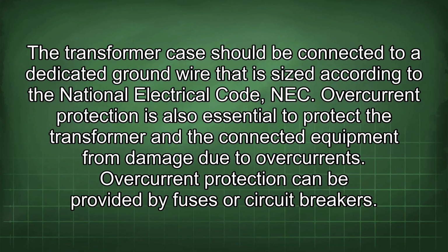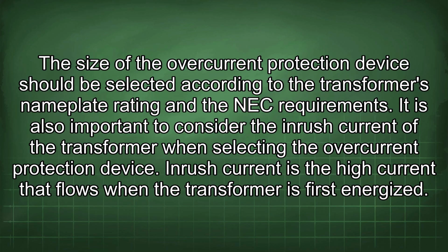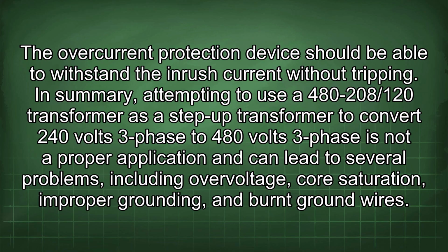Overcurrent protection is also essential to protect the transformer and the connected equipment from damage due to overcurrents. Overcurrent protection can be provided by fuses or circuit breakers. The size of the overcurrent protection device should be selected according to the transformer's nameplate rating and the NEC requirements. It is also important to consider the inrush current of the transformer when selecting the overcurrent protection device. Inrush current is the high current that flows when the transformer is first energized. The overcurrent protection device should be able to withstand the inrush current without tripping.